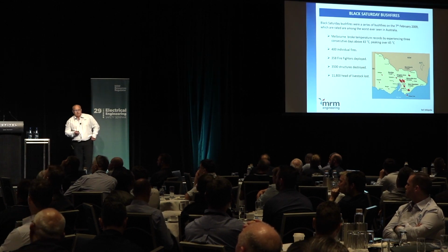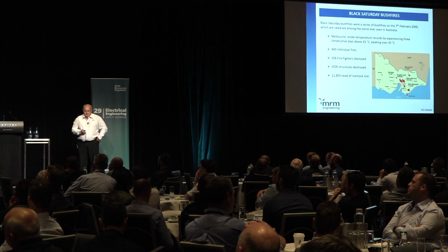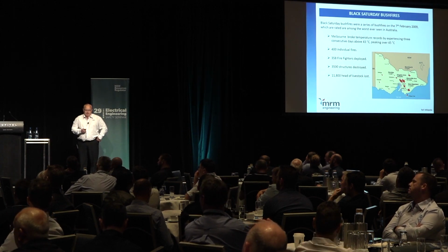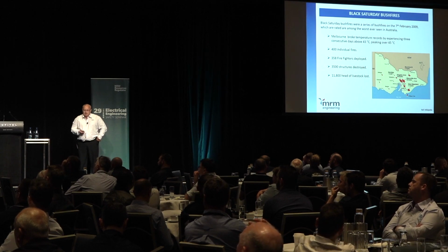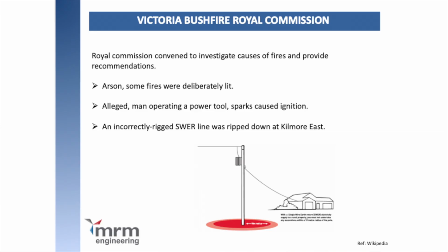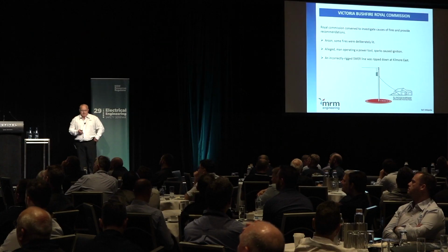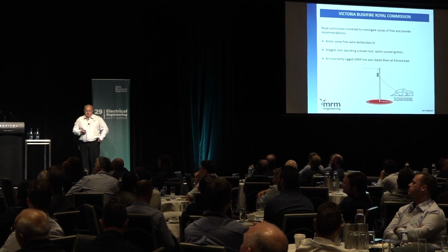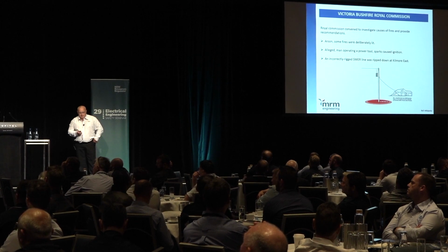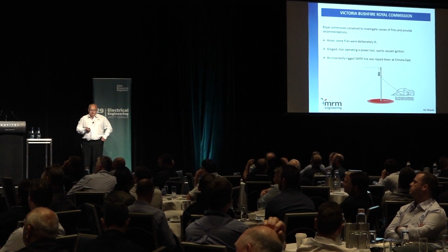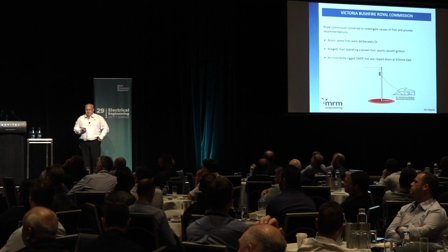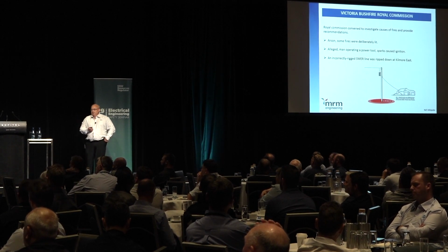This is probably topical at the moment when you see the bushfires we're having in New South Wales and up in Queensland. So from that, Victoria developed a Bushfire Royal Commission, and they did a review on a lot of the instigation or the starting of the fires. So arson, with some of the fires deliberately lit. A man allegedly using power tools caused sparks to cause one. And then one of the things that started the rapid earth fault current limiter investigation off was an incorrectly rigged SWER line that was ripped down at Kilmore East substation. So it fell down and created sparks and initiated the fire.